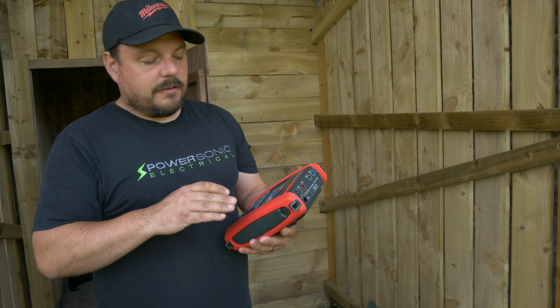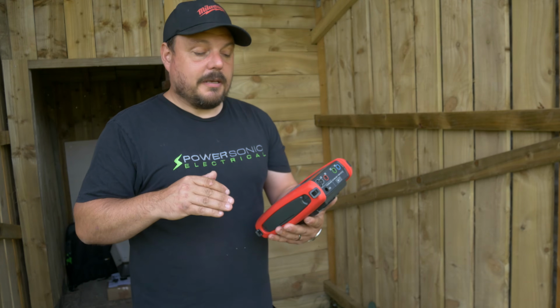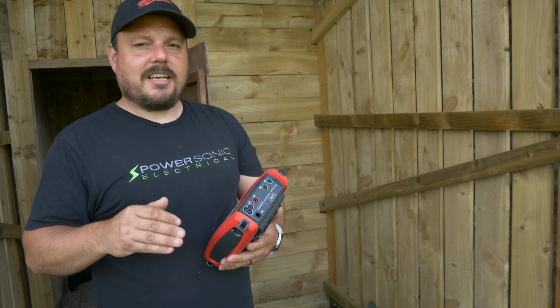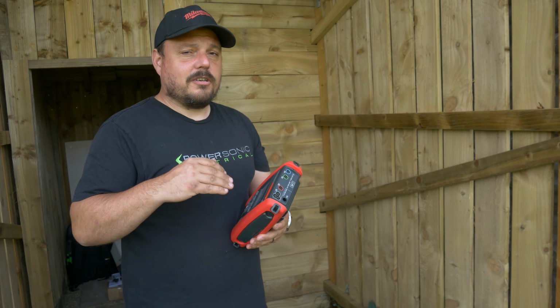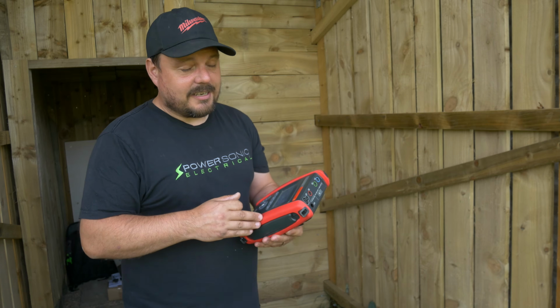There's the auto mode for your ZE, ZS and your PFC, PSC and RCD tests. So if you want to leave the instrument and run through and do those tests automatically, you can do.